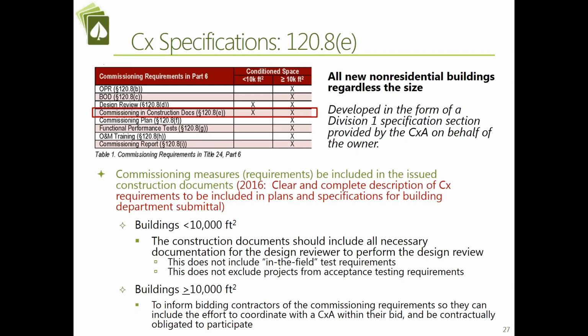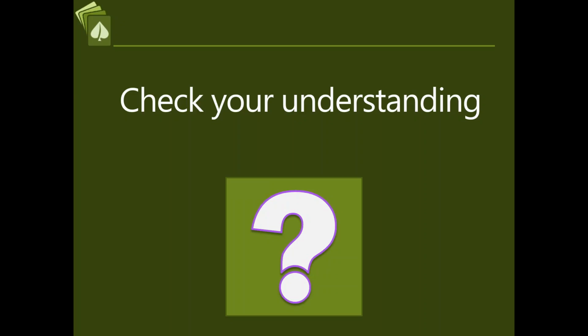Well, that's where that flavoring of acceptance testing comes into play. Acceptance testing has to be done, like I said earlier, for all building types. And that acceptance testing is going to be done by a particular licensed contractor in the field testing their work or someone else's work. If the building is over 10,000 square feet, well then the commissioning specifications might be saying, above and beyond what California requires in terms of acceptance testing, we're going to also require these other functional testing to be provided, and this is who is going to be doing that and when it is going to be required throughout the project.